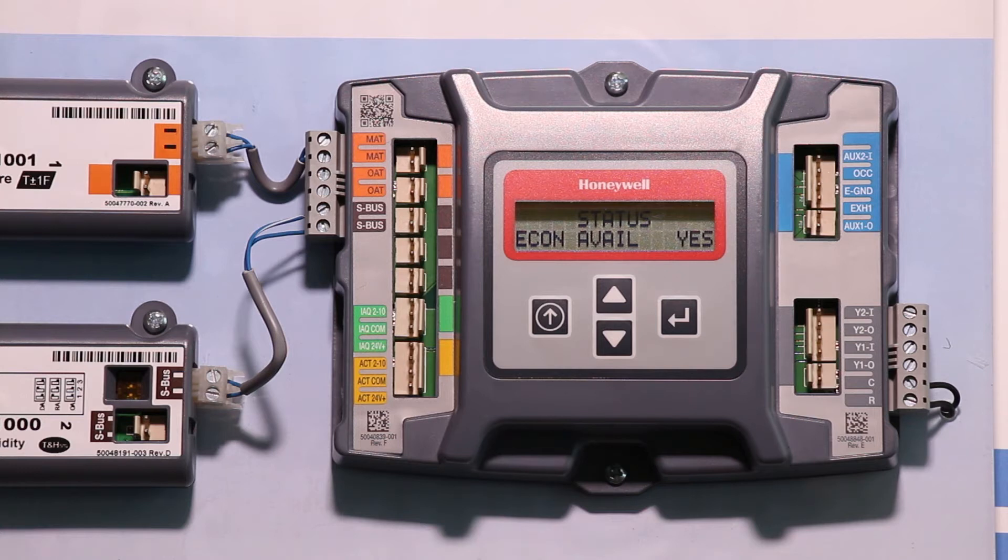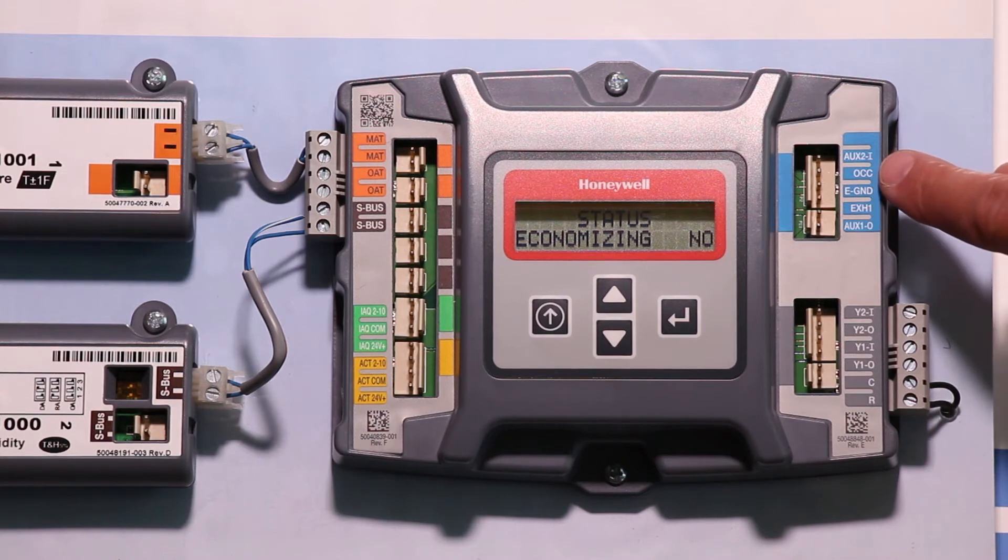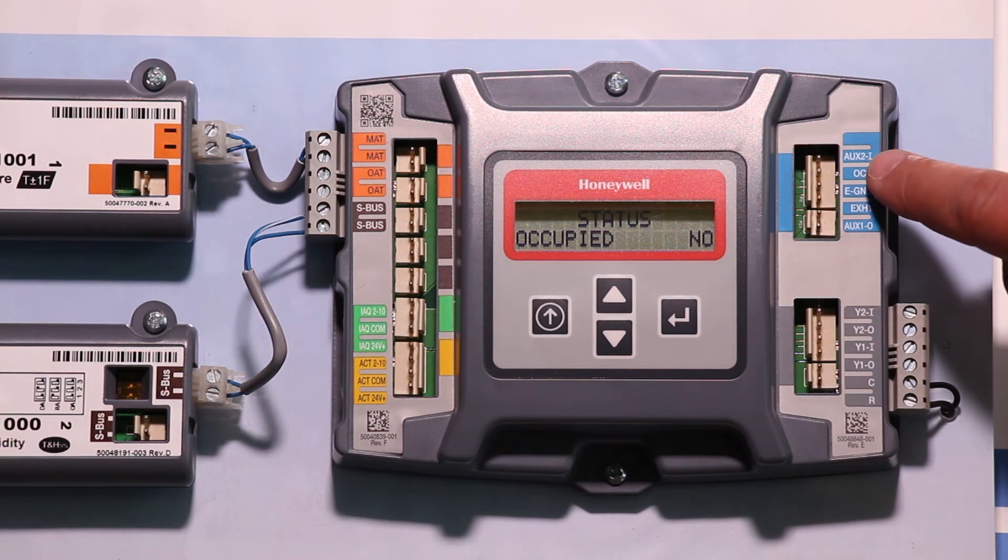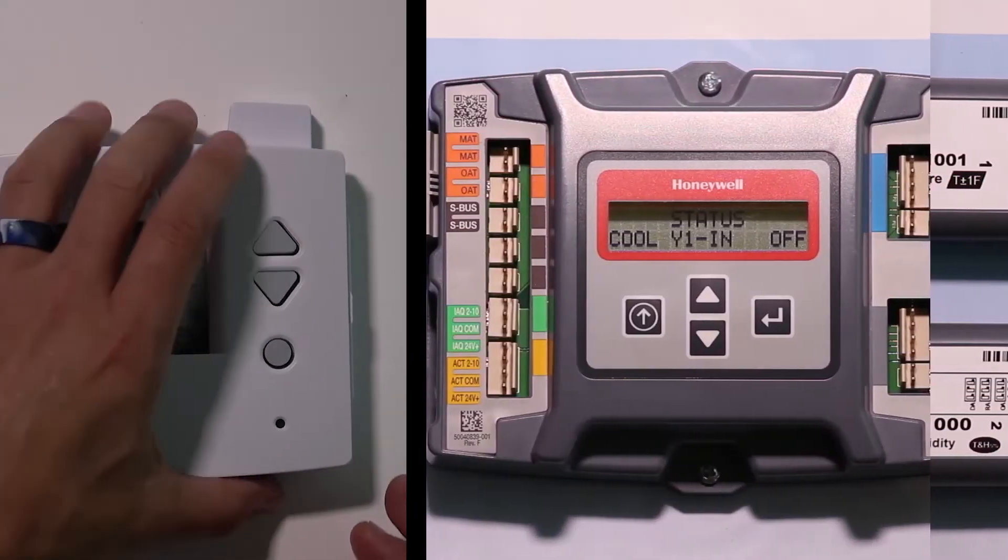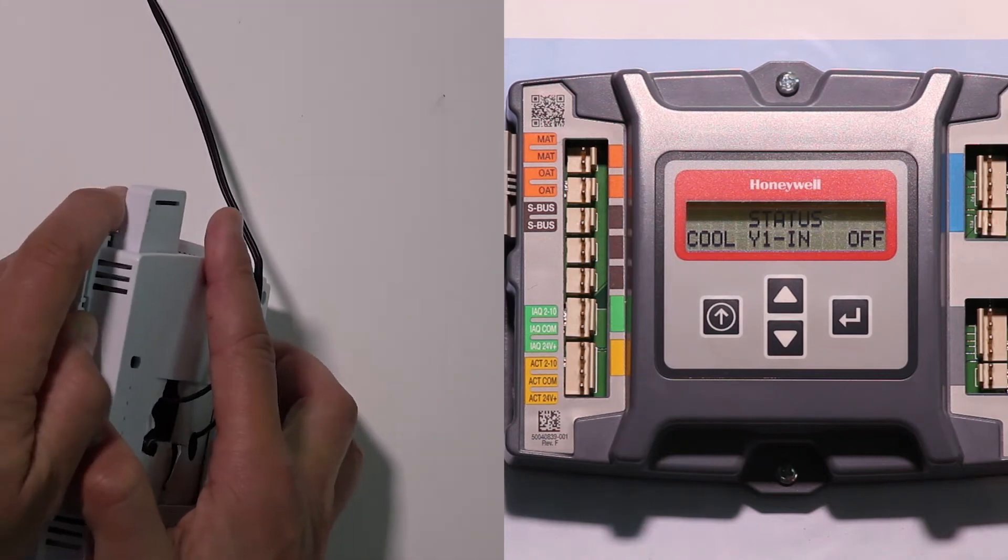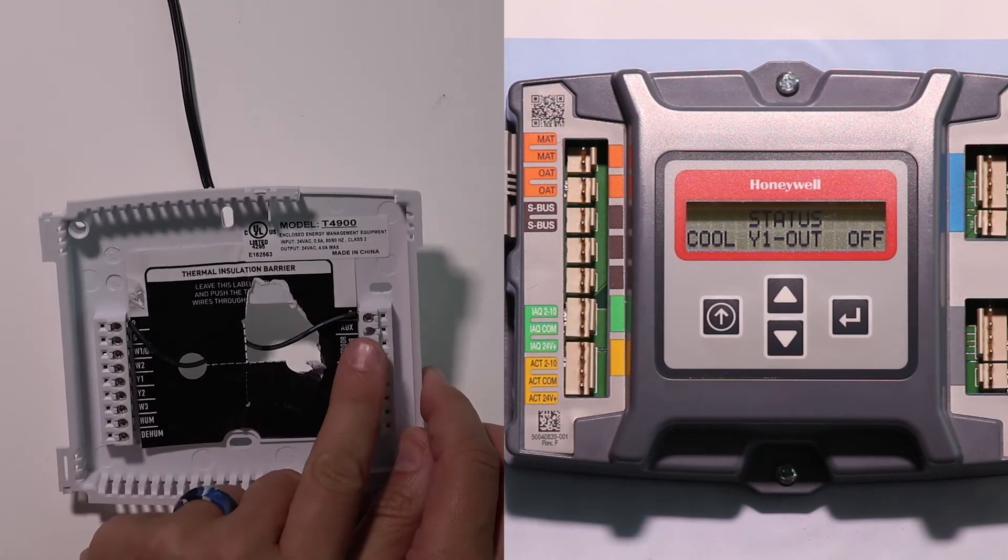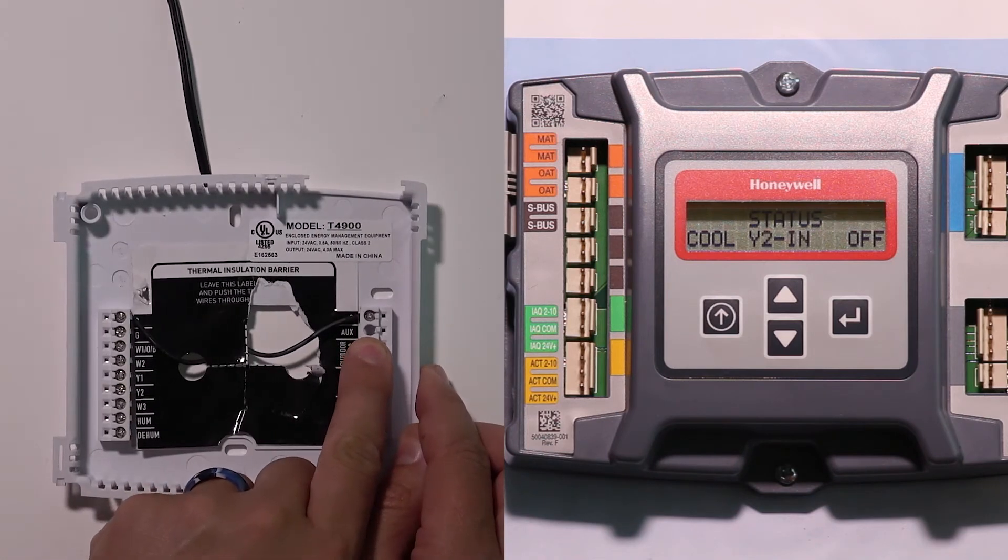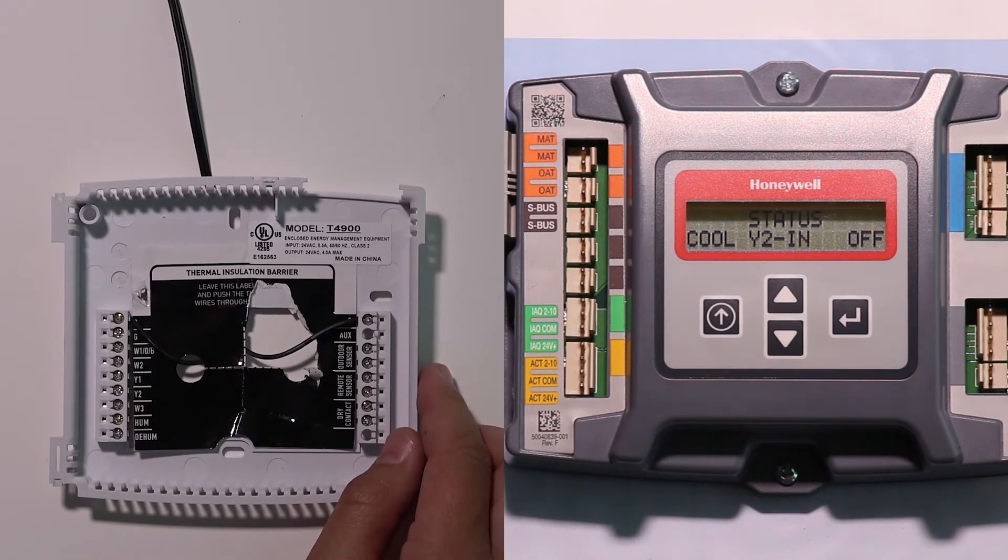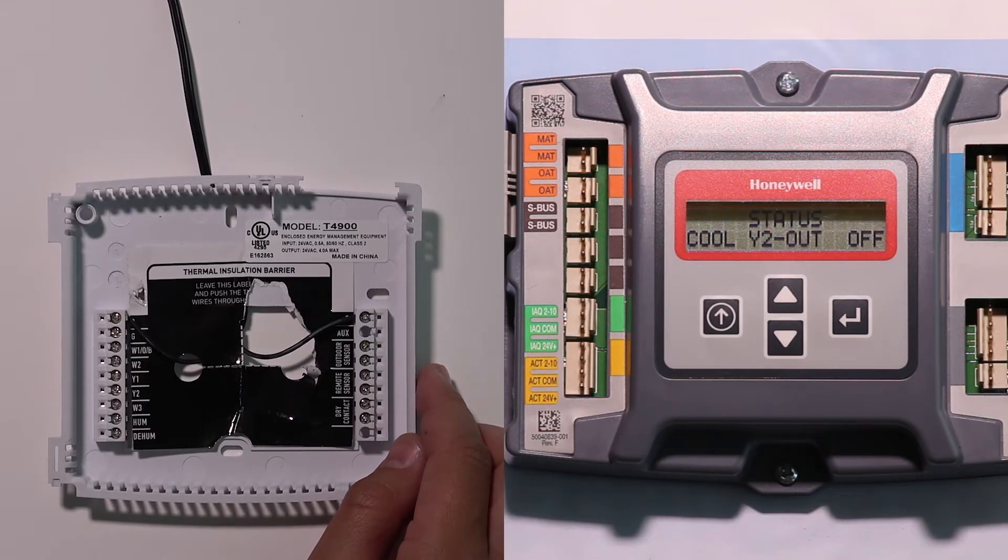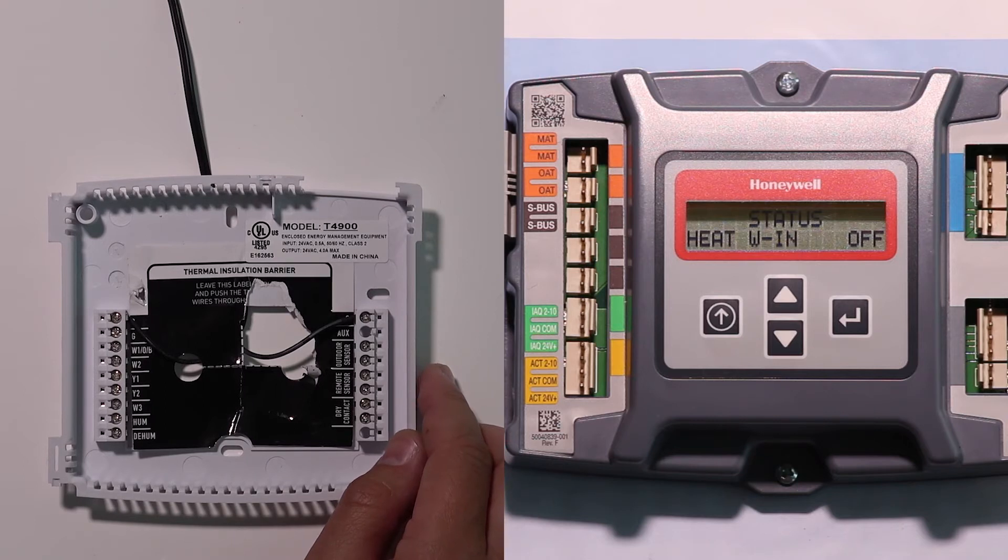So from a wiring standpoint, over here on our economizer controller we have a terminal labeled OCC for occupancy. That is an input terminal. It is waiting for a signal from somebody to tell it he is occupied. Then on our thermostat, if we pop him open and take a look at the inside here, we have this AUX terminal on here. That's a flexible terminal that we can program to do whatever we want. In our case, we're going to program it to be an output based on time schedule. So let's go ahead and do that now.